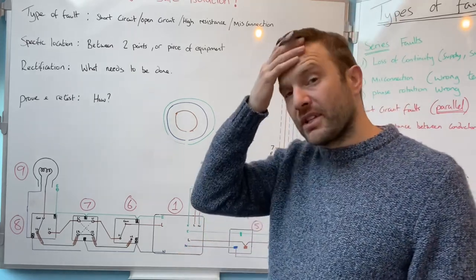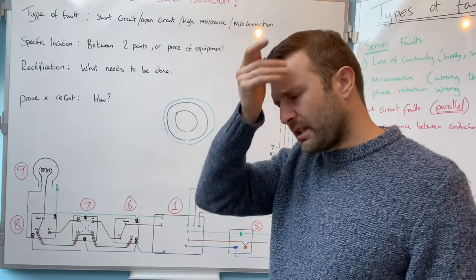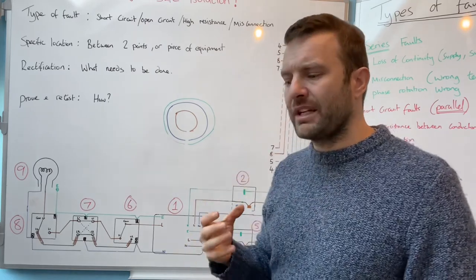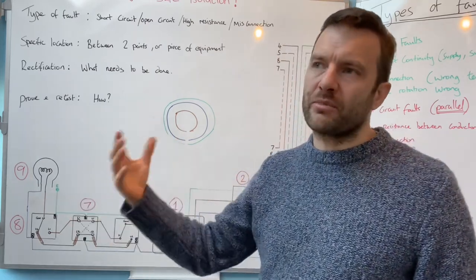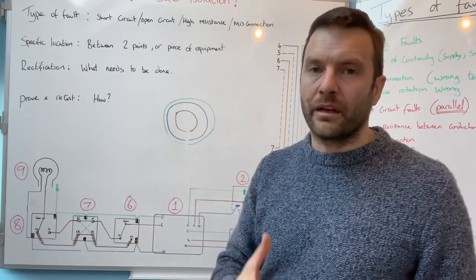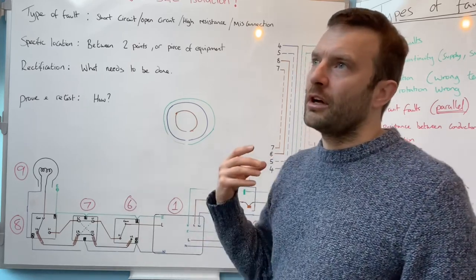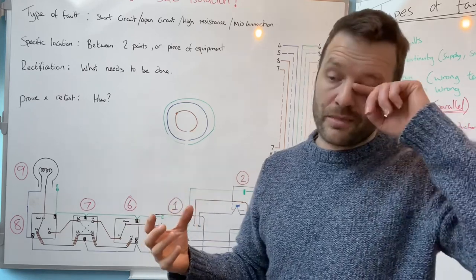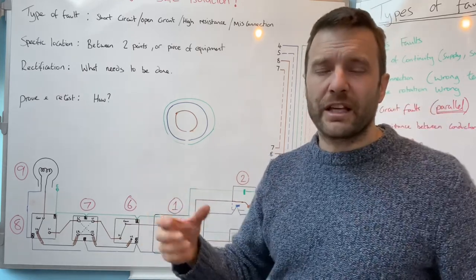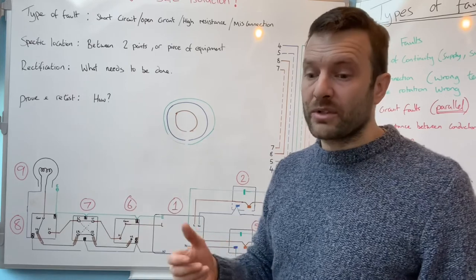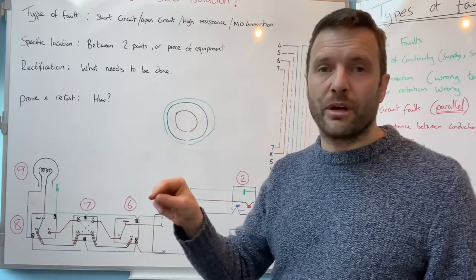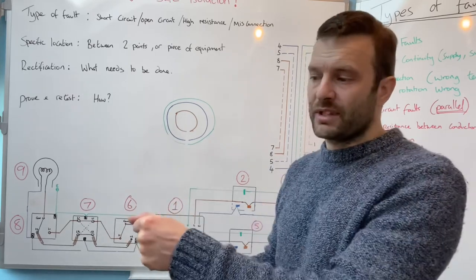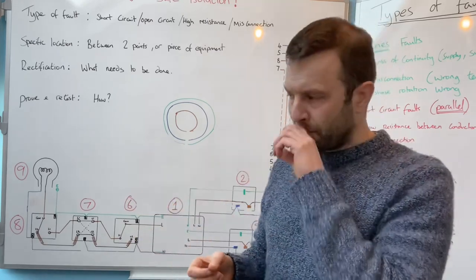If you're testing the boiler system, I'll just finish with this. If you're testing the boiler system, don't forget that you need to test the accessory separately to the cable, if you can. So for instance, a pump on a heating system, they don't usually come flexed. You've got to flex them up. Most these days have push-in terminals. So literally like Wagos, you push the tab down, you pull the terminal out.